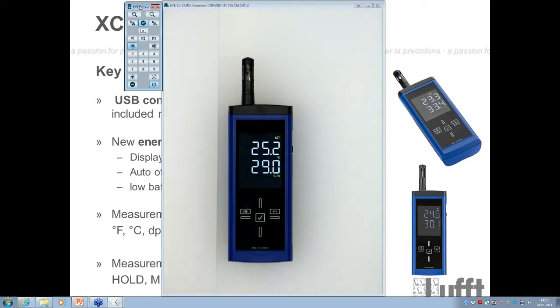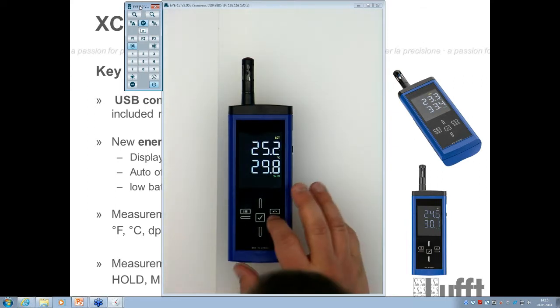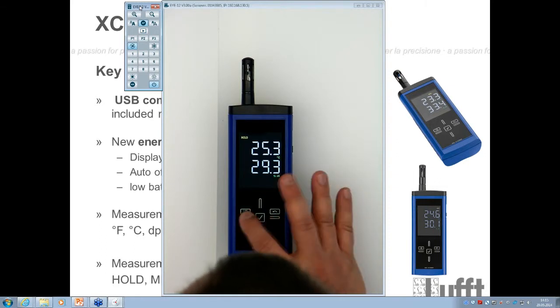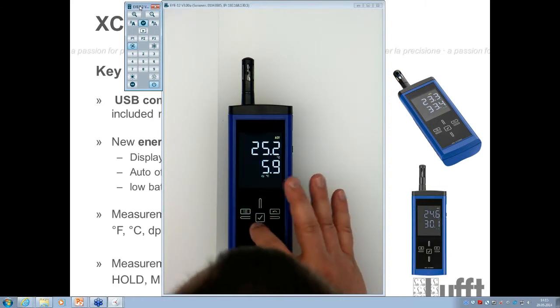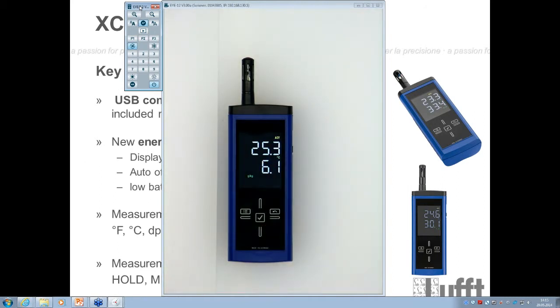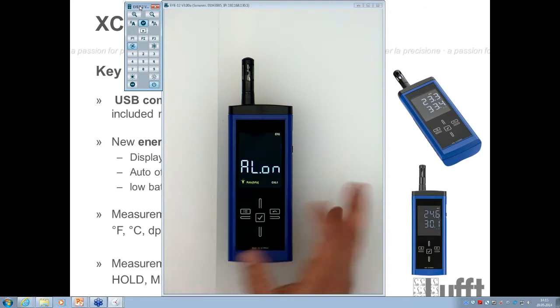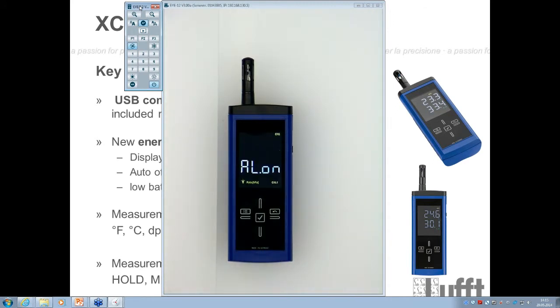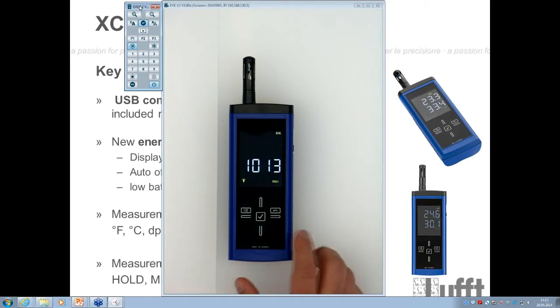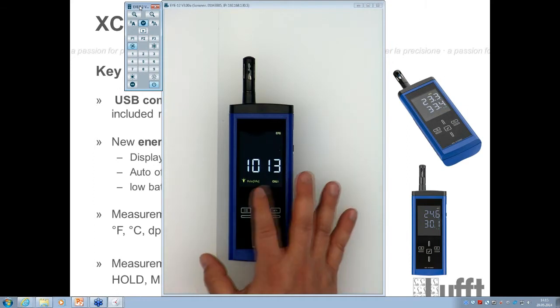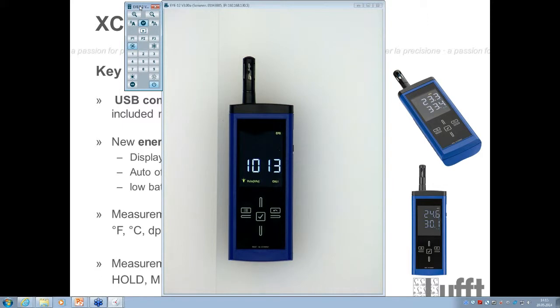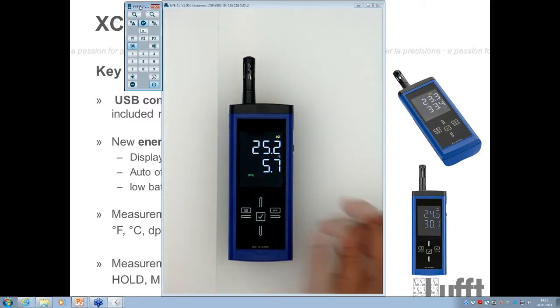So now, for example, you want to change the mixing ratio. Then you have, of course, first of all, to switch to mixing ratio, for example, gram per kilograms. Then you again go to the configuration menu, and you see now we have an additional configuration possibility, which is the absolute pressure I told you before. And now if you go with the left and right keys to absolute pressure, then you will be able to enter the pressure, and then the value will be calculated with this value, of course.